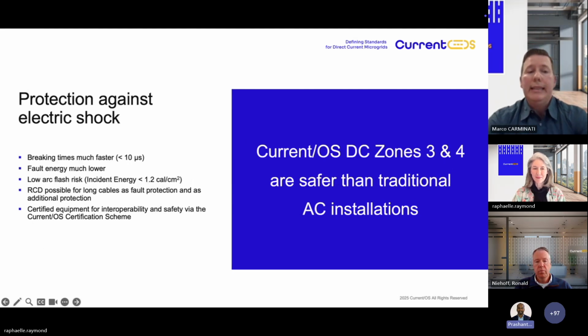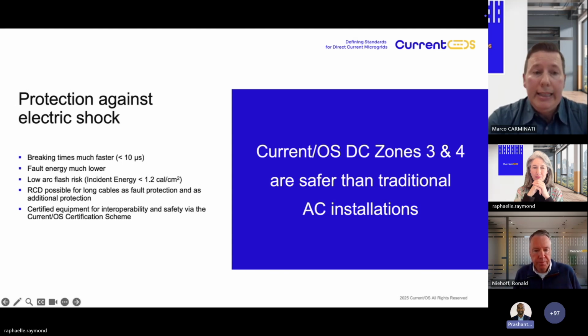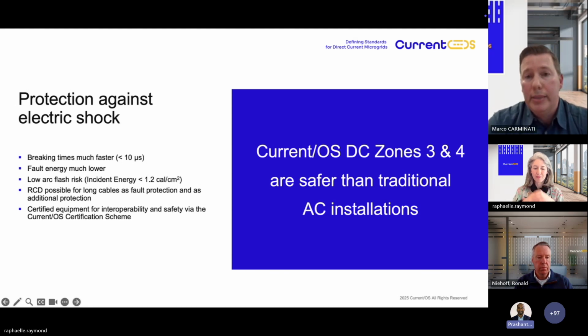So, some words regarding the protection against electric shock. In particular, let's focus on Current/OS DC Zones 3 and 4. First of all, the breaking time is much faster as we have solid state devices, so less than 10 microseconds. And the related fault energy is much lower, which can bring a lower arc flash risk, as the incident energy is usually lower than 1.2 calories per square centimeter.